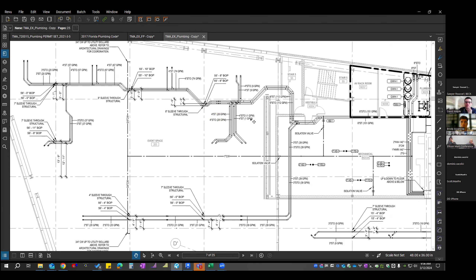That's why there's all these offsets, they're not totally arbitrary. It's about a 1 foot by 2 foot diameter around that bus port, is what you're describing, David. It's rectangular, the conduits go in east-west directions and not north-south, so it's a little tighter in one direction than the other. So we oriented them that way, the orientation is actually quite important to consider. You'll see that in our Revit model we shared. I think our boxes might be hidden as a component, but they were modeled with that kind of no-fly box.